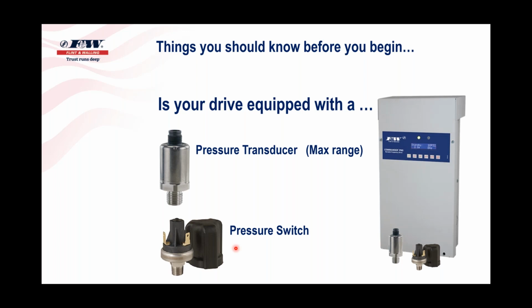We come back from that show, we set the drive up, and within a very short period of time with some software changes, we now have a drive that'll operate either off the pressure switch at the bottom or the pressure transducer at the top. And I'm going to just share an opinion with you, and it's just my opinion. I wouldn't expect Flint and Walling to endorse this, but in my opinion, this pressure switch is dying a slow death. It really is, because this pressure transducer is much more popular. And like a guy told me, he said, you know, I don't like this pressure switch for a couple of reasons. Now, they're not life and death, but I'm going to explain to you what those reasons are here shortly.